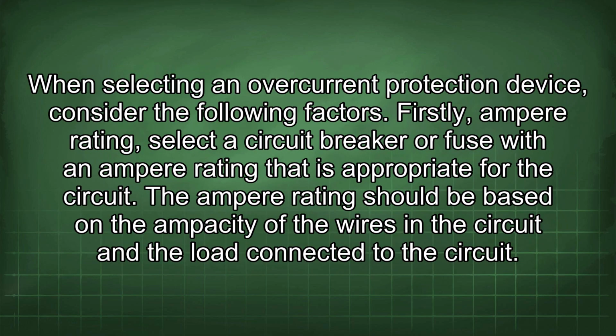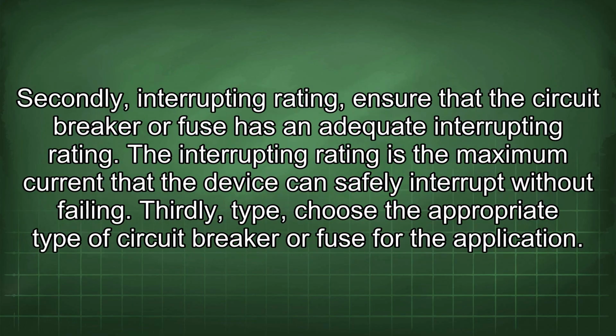When selecting an overcurrent protection device, consider the following factors. Firstly, ampere rating. Select a circuit breaker or fuse with an ampere rating that is appropriate for the circuit. The ampere rating should be based on the ampacity of the wires in the circuit and the load connected to the circuit. Secondly, interrupting rating.